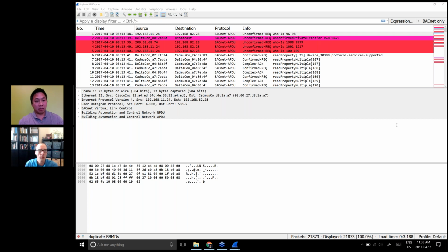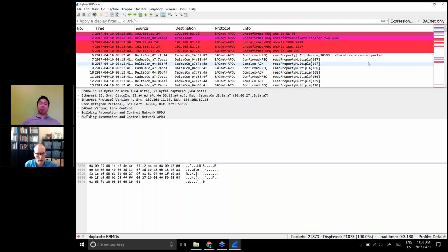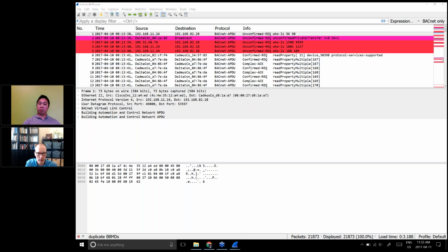The problem with this is, especially in a multi-vendor case, if you have more than one BACnet vendor working on your particular site, BBMDs are often a requirement, but if the different vendors and contractors are not synced up properly in terms of who's doing what, you can end up with a situation where there are two BBMDs on the same IP subnet. Now, in an IT sense, you might think, hey, that's great, I got redundancy. No, you don't, you have an explosion.